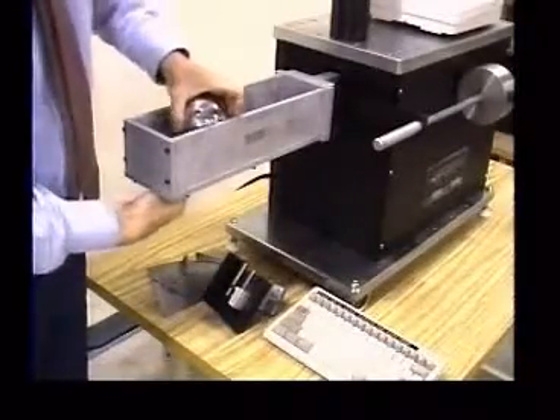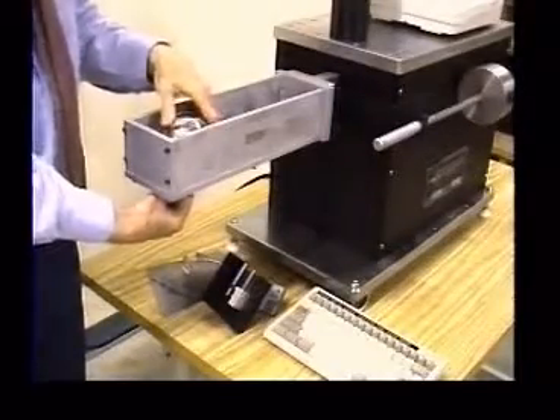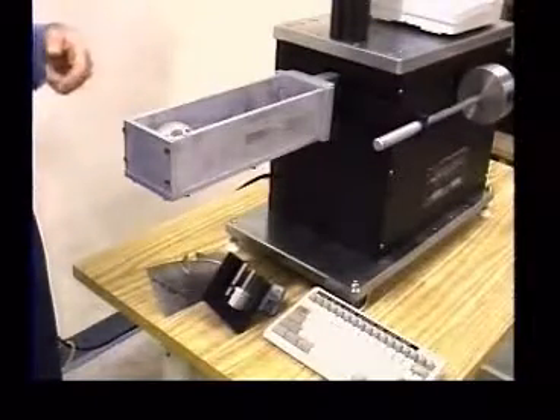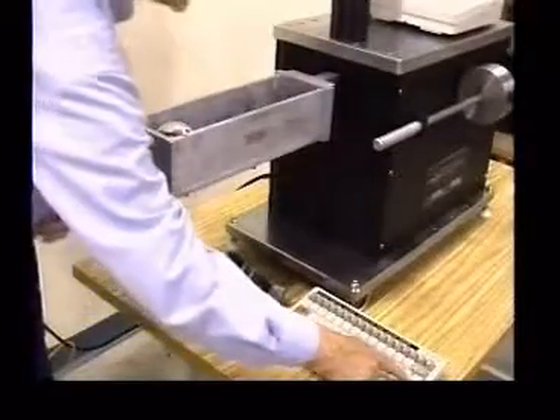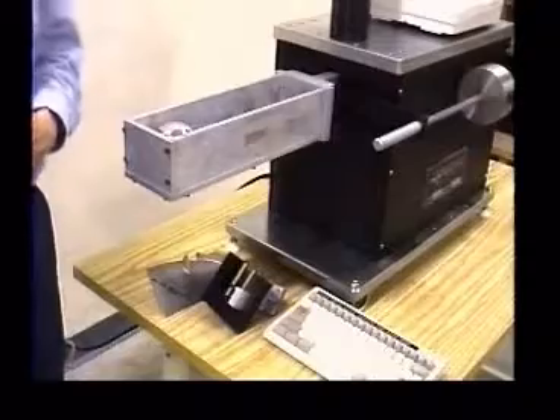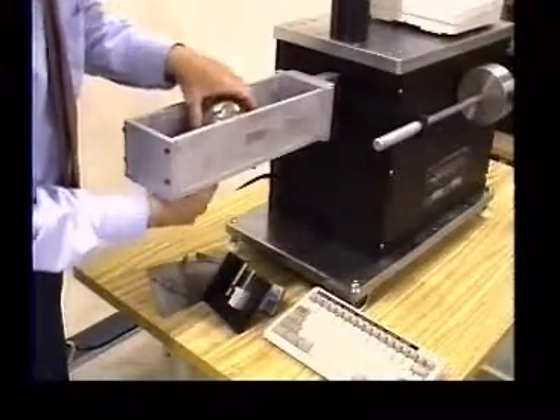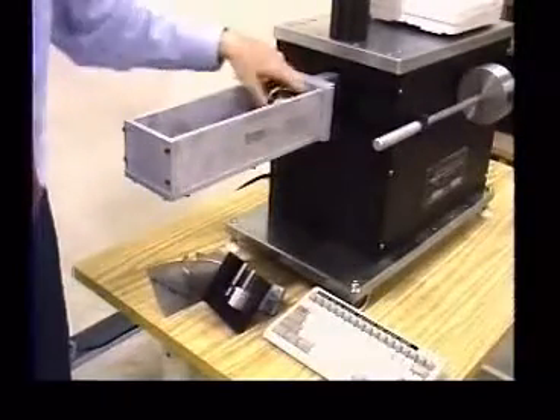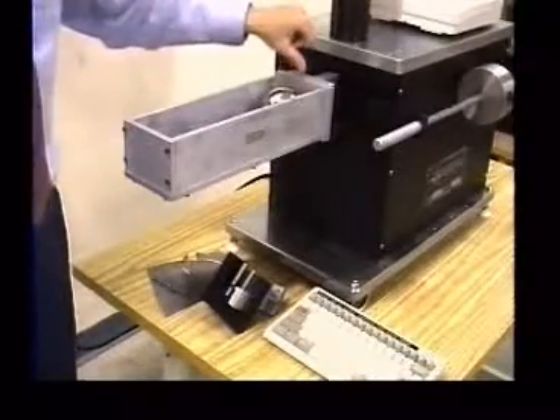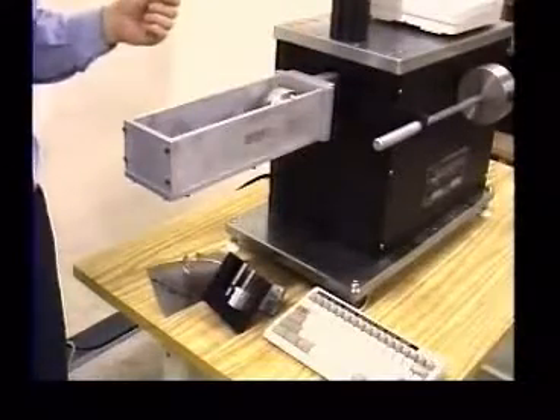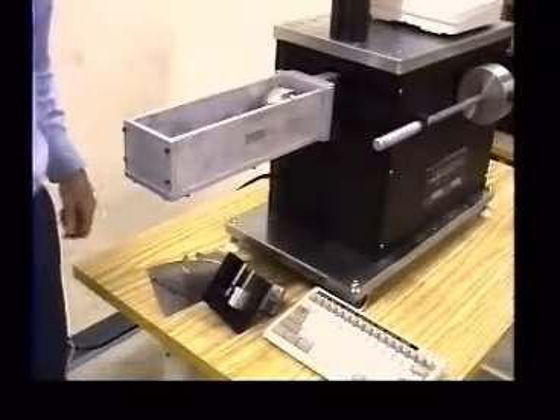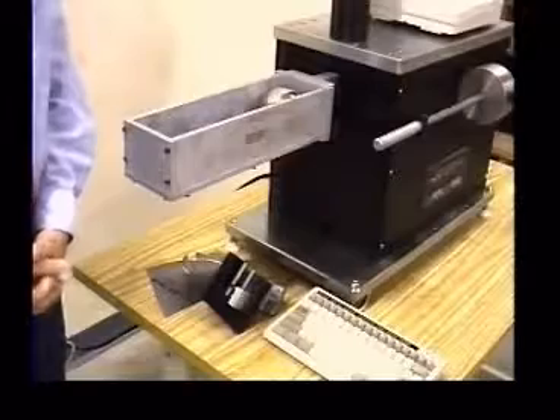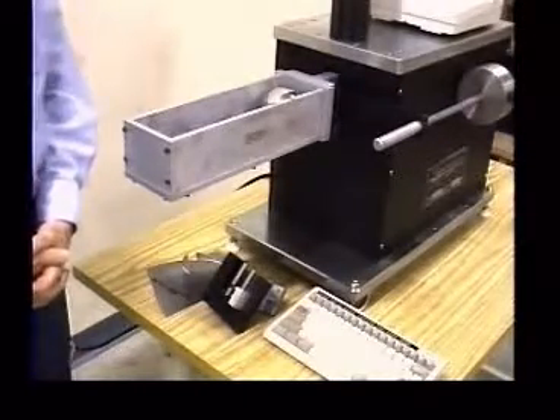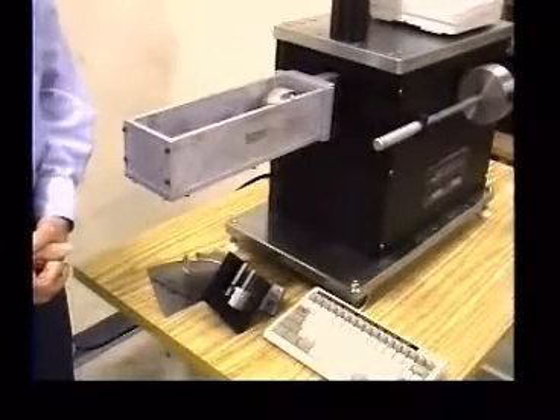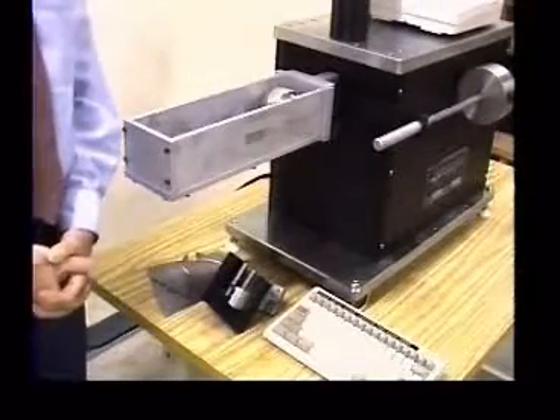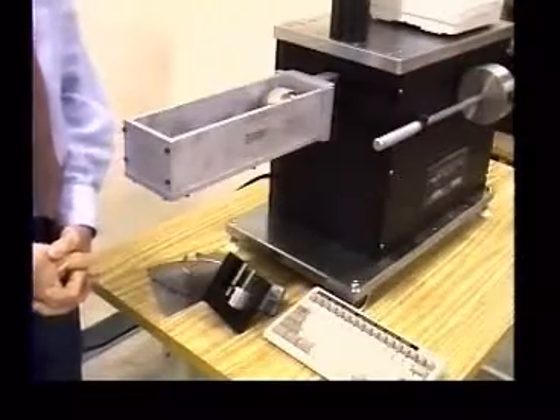The ball is placed in the calibration fixture, and because of the shape of the bottom of this fixture, the ball rolls against one side. The machine then measures a moment, and we press the enter key on the machine to accept that moment. And then I roll the ball to the other side of the cavity, and again the shape of the cavity causes the ball by gravity to press against the opposite surface of the cavity. And then I press the enter key on the computer a second time. The computer now takes the change in measured moment and compares it with the true moment and automatically adjusts the calibration factor of the machine. There's no need to turn threaded weights. There's no need to set gain dials. Everything is performed automatically through the built-in computer in this instrument.